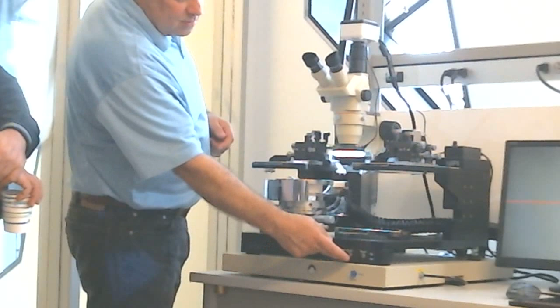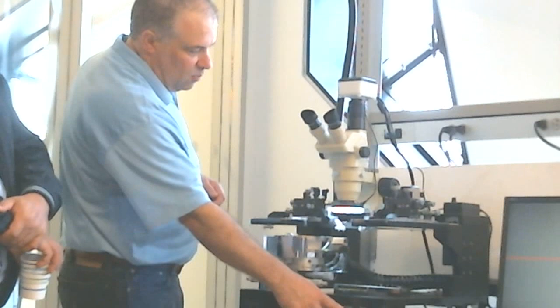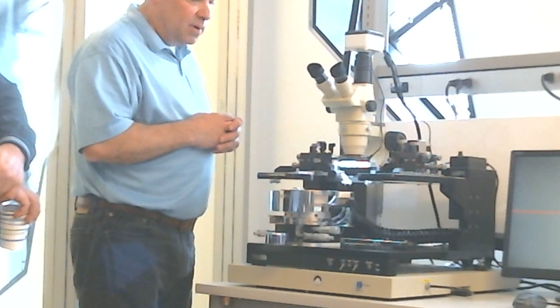When you have it in proper position, there's an aux right vacuum switch and an aux left vacuum switch to turn those on. Once loaded with the vacuum switch on, you can nudge it with your tweezers or whatever you use to load it, and it should fix firmly - make sure you have good contact. These are also very important to keep clean - keep the back of your substrates clean and the surfaces of the aux chuck clean as well. Very, very important for vacuum.